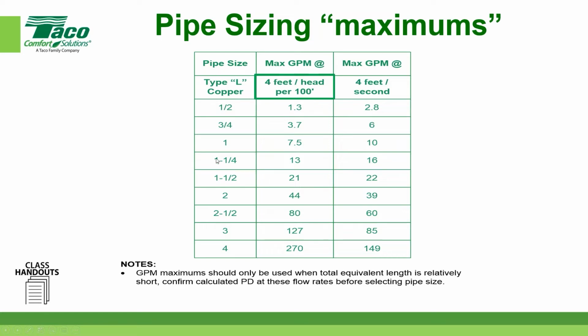So for instance, if I had a piece of 1 inch type L copper and I ran 7.5 gallons a minute through it, notice this is the reference, then the result of that would be 4 foot of head. Now the other one over here is 4 feet per second. This talks about how quickly the fluid's moving through the pipe. Let's stay with 1 inch here. 1 inch, I could push it all the way out to 10 gallons a minute, because at 10 gallons a minute I would be at a velocity of 4 feet per second. Hopefully that makes sense.